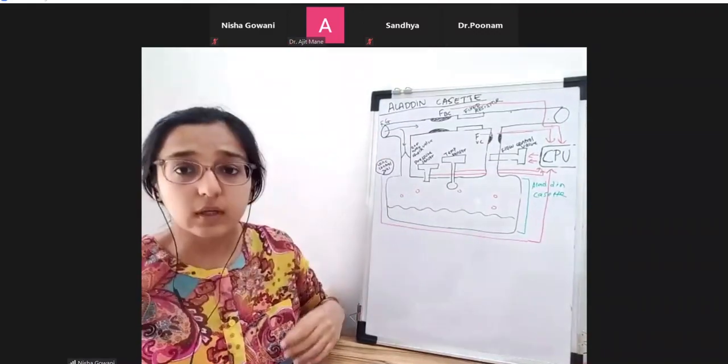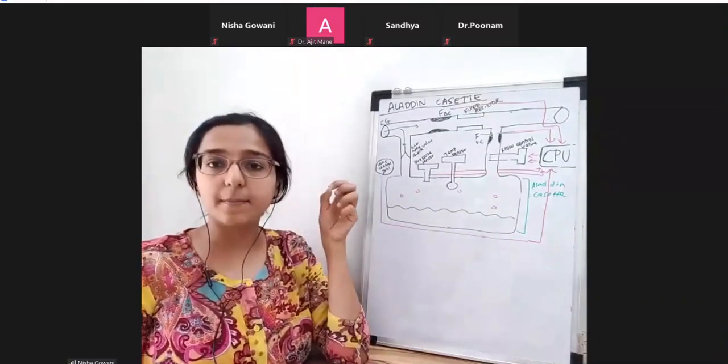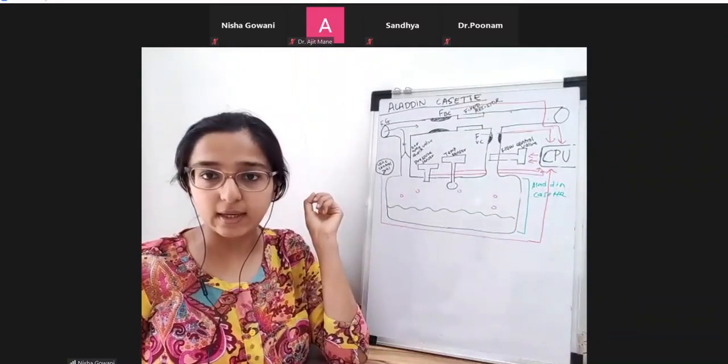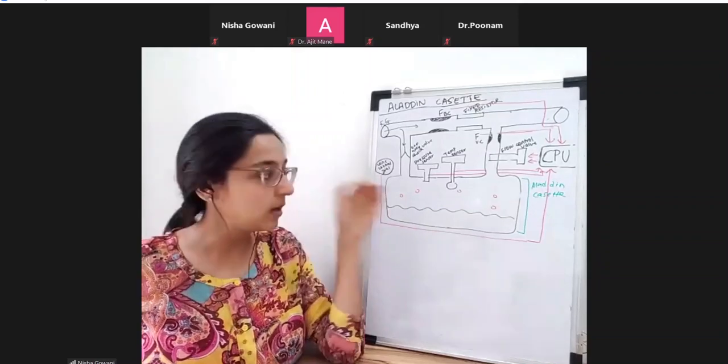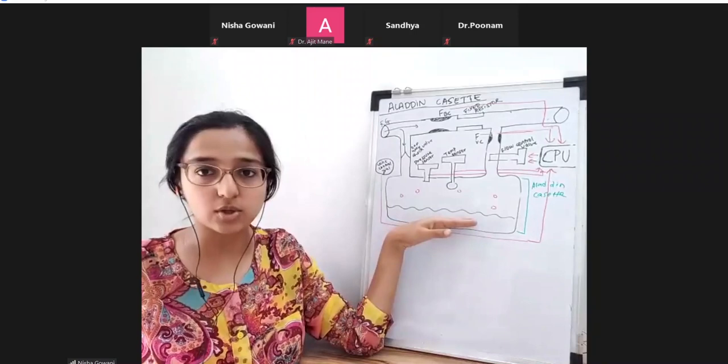Now, how does desflurane work? We know that at room temperature, desflurane will start boiling at 22.8 degrees. So if desflurane over here reaches 22.8, which is around room temperature, it will boil.